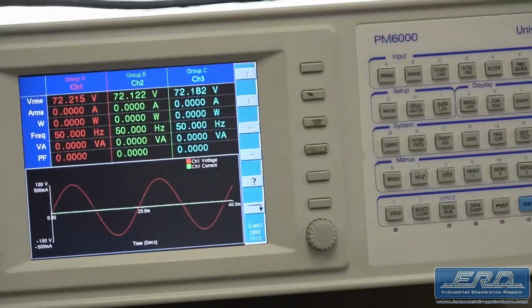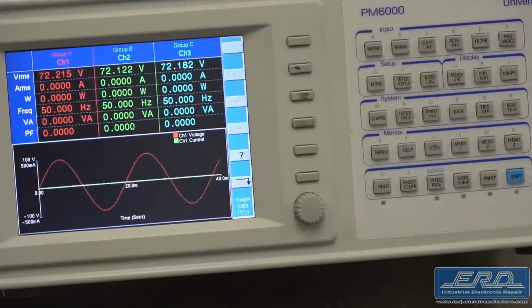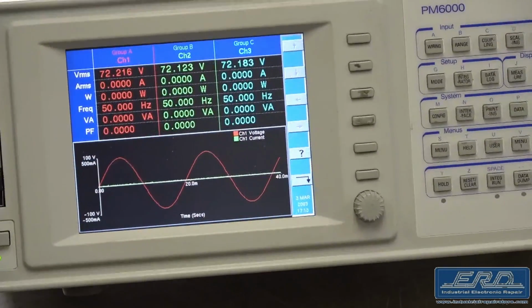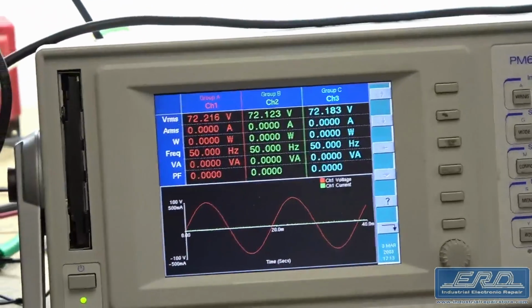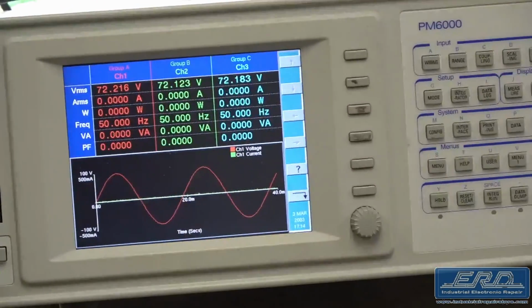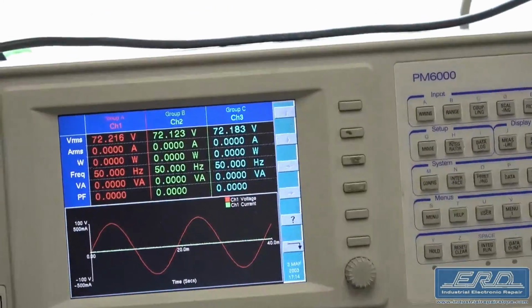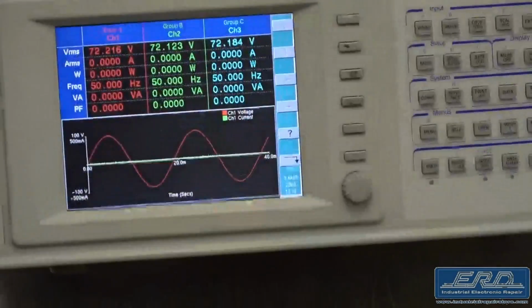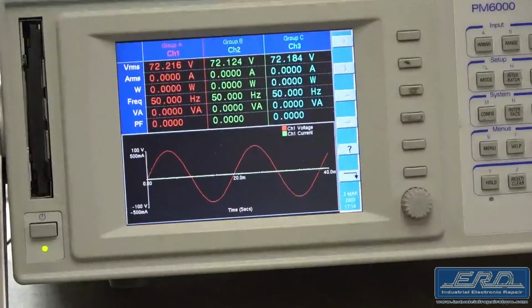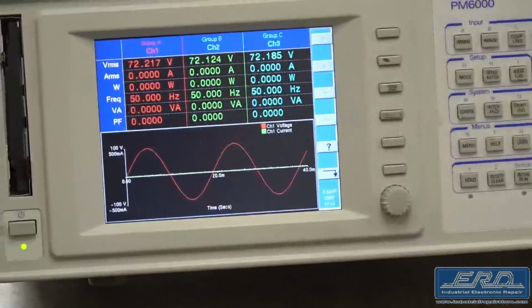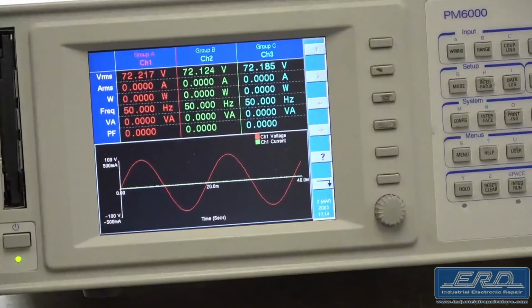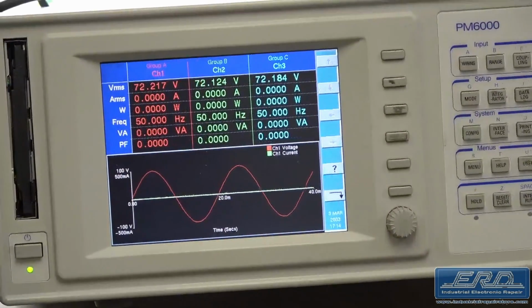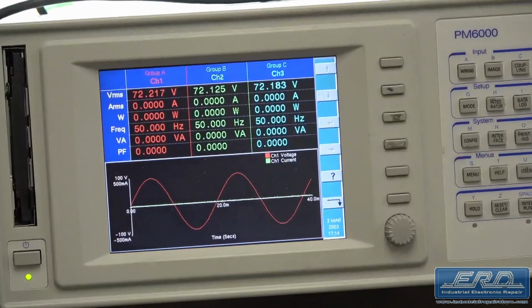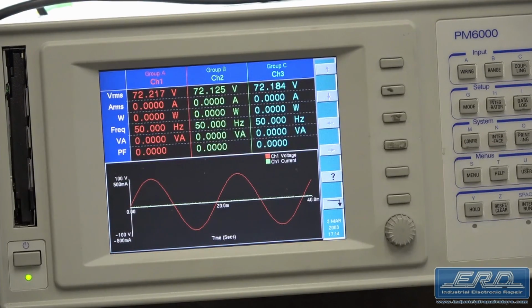The Voltech PM6000 is an up to 6-channel power analyzer used by manufacturers to certify the power requirements of their products and by listing agencies such as CSA and UL. This instrument is a Linux-based computer that has a custom interface with up to 6 input channels, which perform the monitoring. The voltage can be monitored directly by the input board, and a separate input allows for current readings.